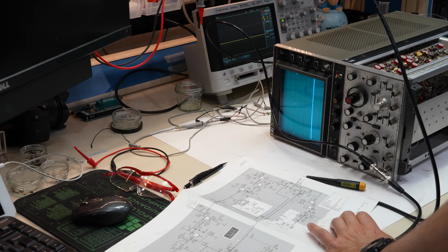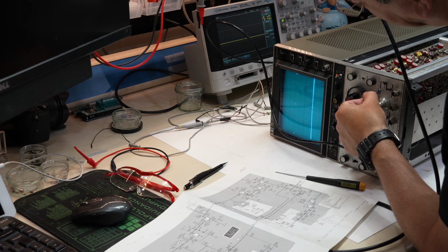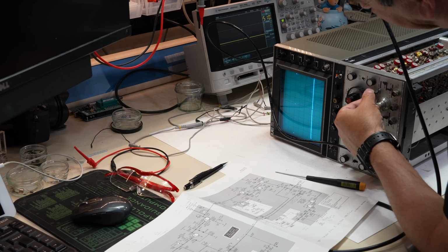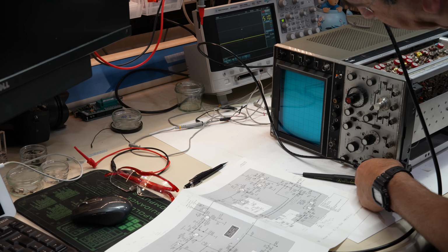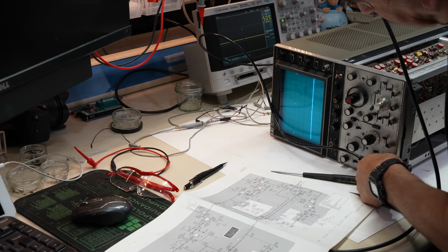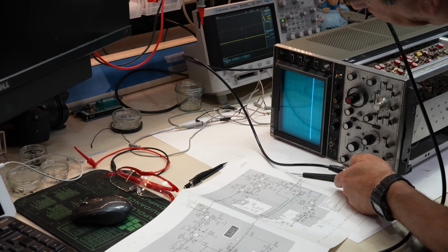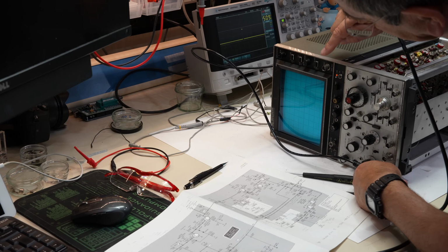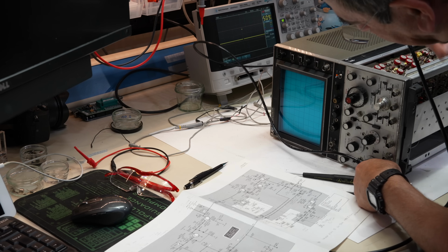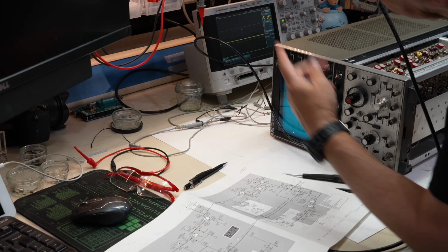A few moments later. So we are now calibrated, and we are left with just one fault, which is that it doesn't do single sweep. It should stop here. So it does the normal, so it can stop the sweep for sure. And then if I do auto, it will sweep in auto. And if I do single, interesting, it stops if I have nothing, but it will still trigger, and it should have only triggered once.